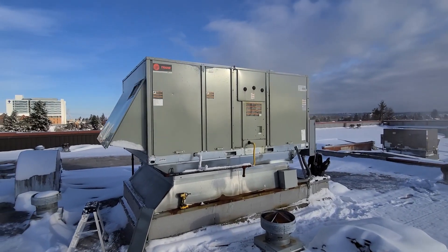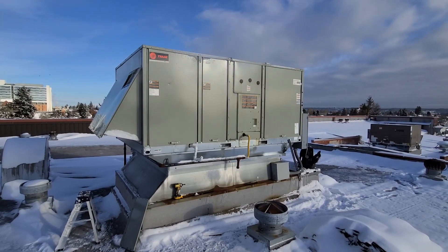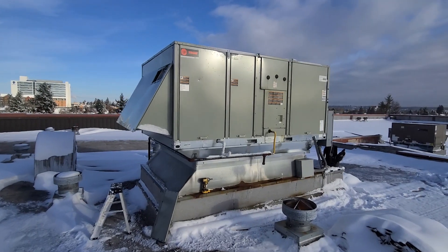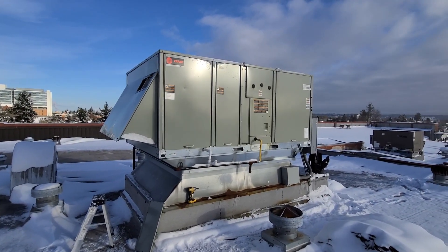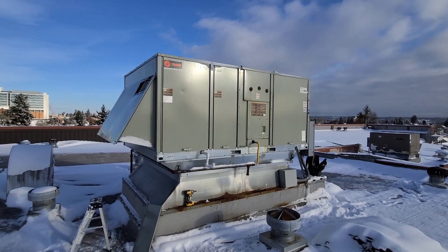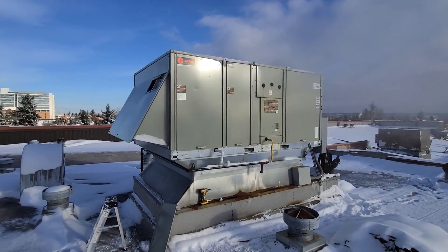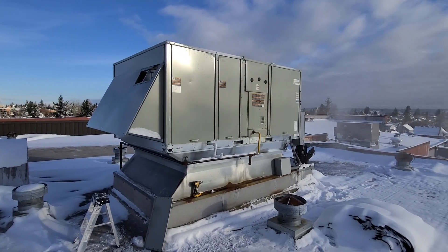I'm getting out here for a service call for no heat on this Trane 15-ton package unit. It's a gas pack, so we have gas as our main source of heat. This is one of our maintenance customers. The system is also on a zoned system that I can pull up remotely, so I pulled it up and could tell that it was trying to heat — it just wasn't keeping up.